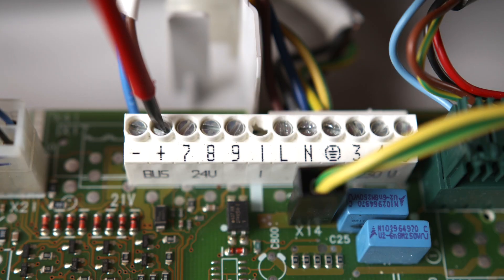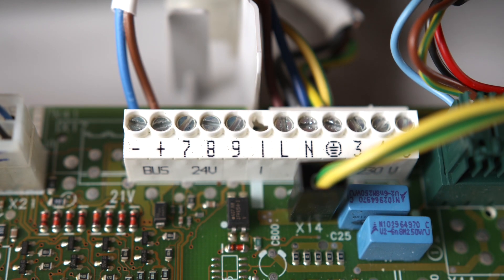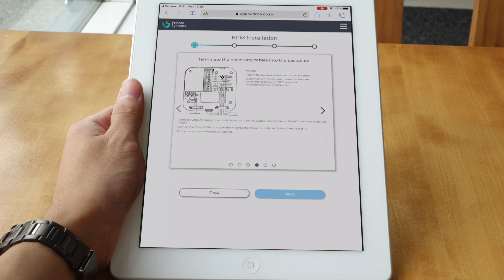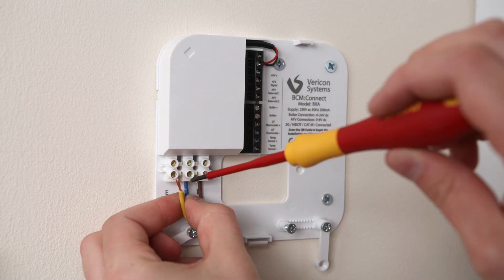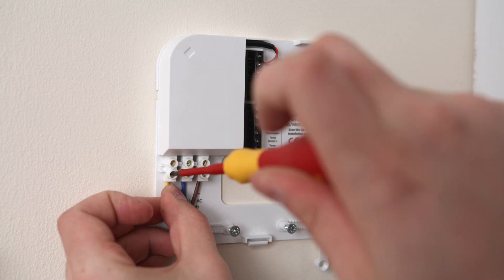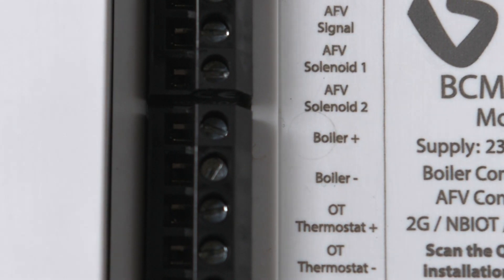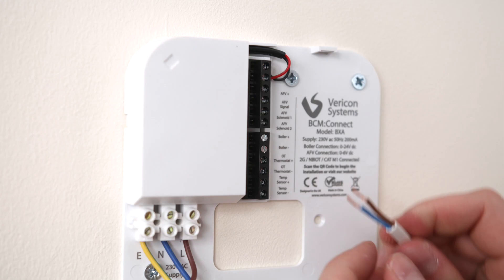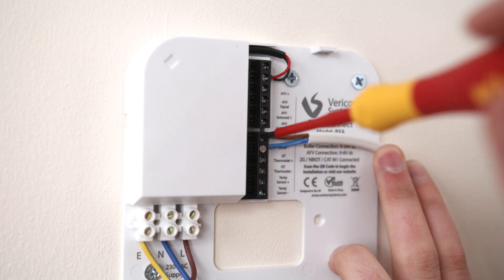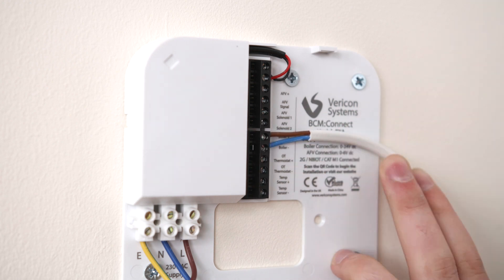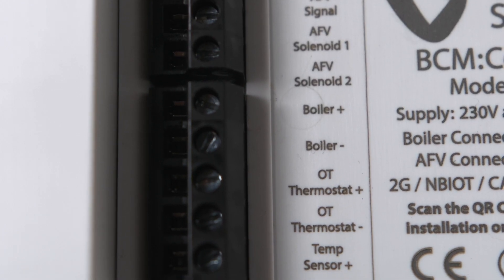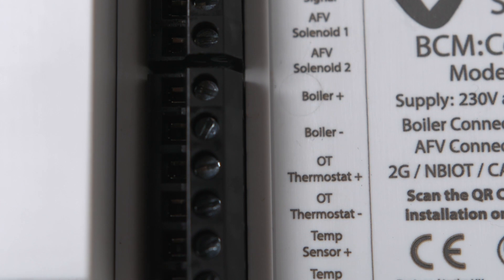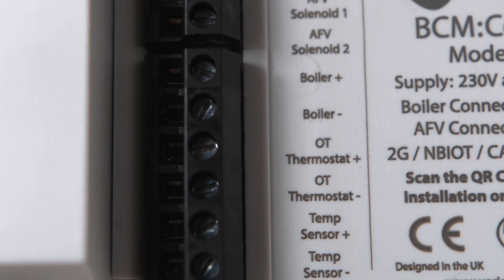Next, connect the boiler bus cables into the relevant terminals on your boiler. We will now connect the wires into the BCM's backplate. The 230 volt main supply is terminated on the left hand side. The boiler bus connects into the boiler plus and boiler minus connections on the 12 way header. If an OpenTherm thermostat was connected to the boiler, this should be connected to the OT thermostat plus and minus connections. If you also purchase an autofill, this will be wired into the BCM backplate. However, this will be covered in a separate video.